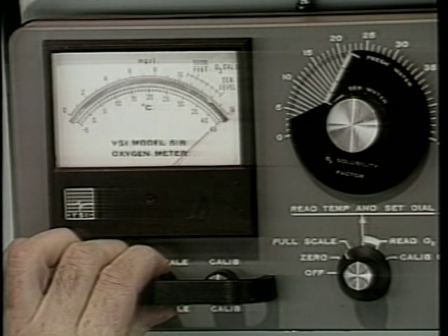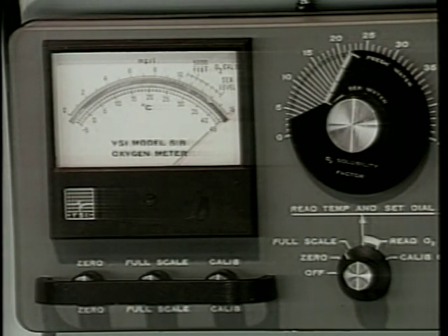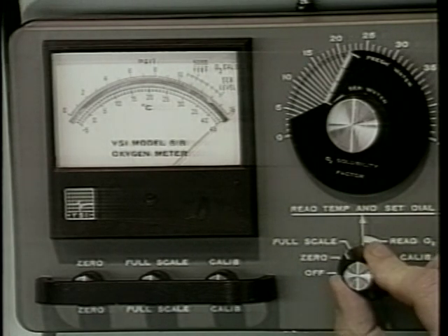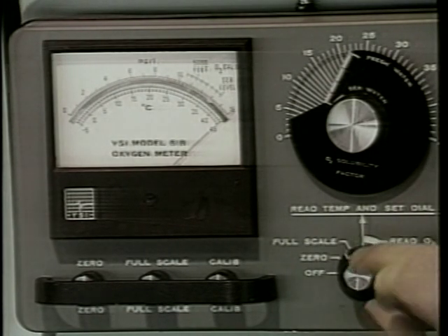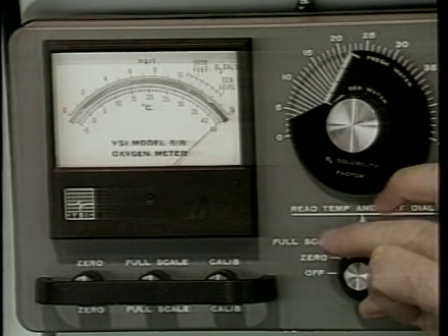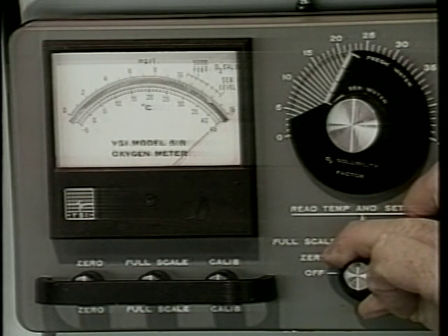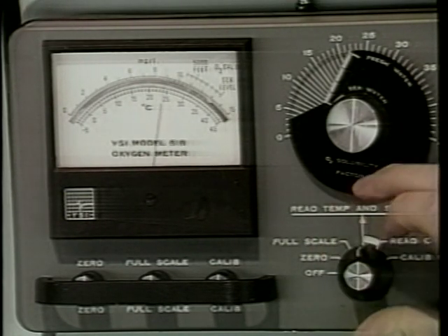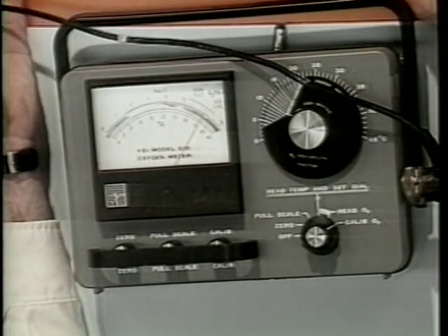This adjustment is similar to the red line adjustment of the other type meter and is a check for battery strength. If a full scale reading cannot be obtained, the batteries need to be recharged or replaced. At this point, the operation of each meter will be discussed separately.